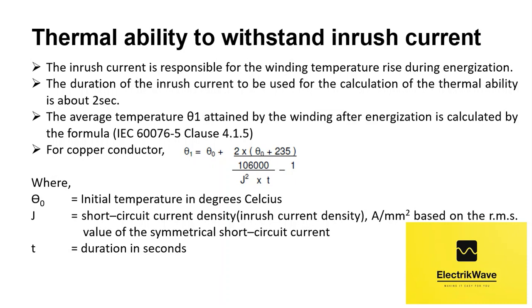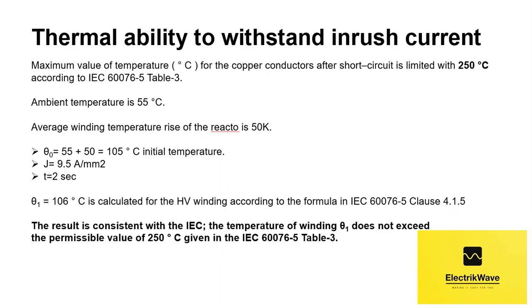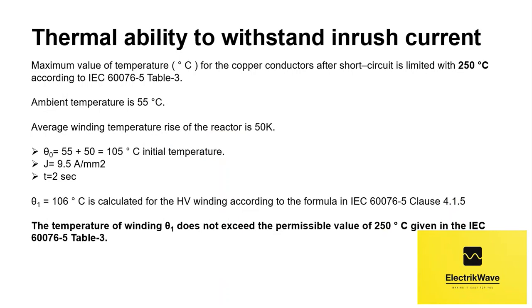Where theta_0 equals initial temperature in degrees Celsius; J equals short circuit current density, which is inrush current density in ampere per mm², based on the RMS value of the symmetrical short circuit current; T equals duration in seconds. Maximum value of temperature for the copper conductors after short circuit is limited to 250 degrees Celsius according to IEC 60076-5, table 3. Ambient temperature is 55 degrees Celsius.